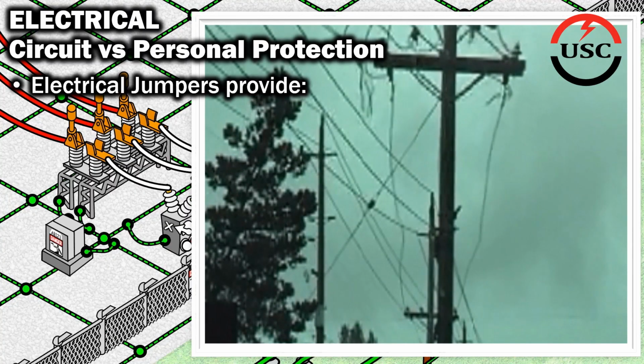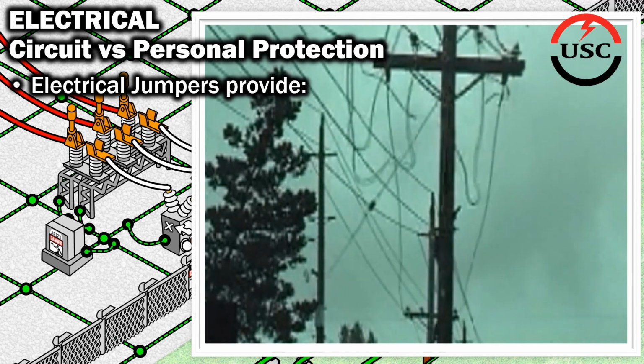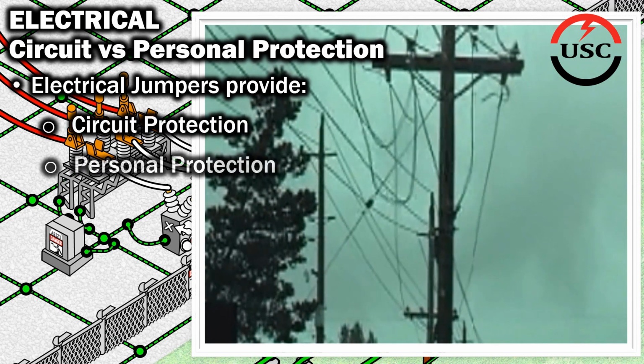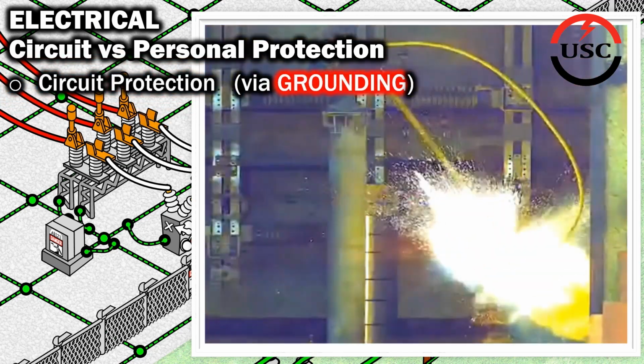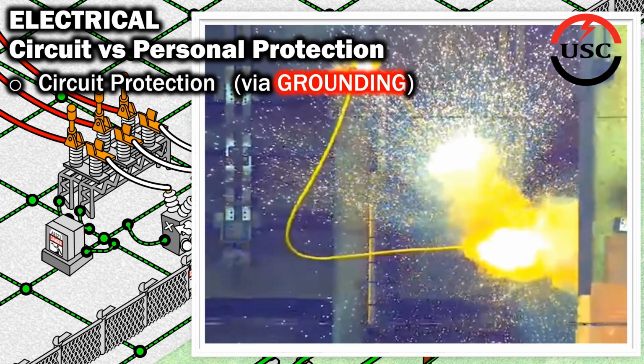Electrical jumpers are arranged on a de-energized system to provide either circuit protection or personal protection or both. Circuit protection is a form of grounding. Its primary objective is to prevent any damage or further damage from being imposed on the electrical system by minimizing fault current duration time, measured in electrical cycles.